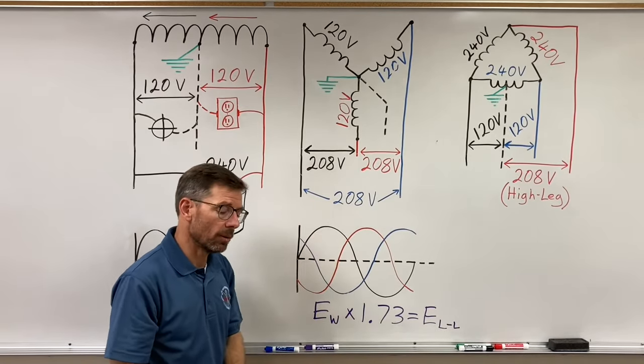Black to red, red to blue, blue to black — those are our three-phase loads. The main reason we run three-phase is efficiency: I can carry more power for the amount of copper I'm using, a better return on investment. We also get smoother running power for motors, more evenly balanced than single phase. So for larger loads, we tend to go three phase — three differences of potential.